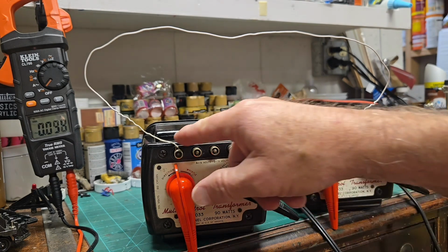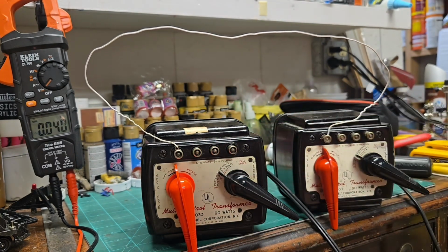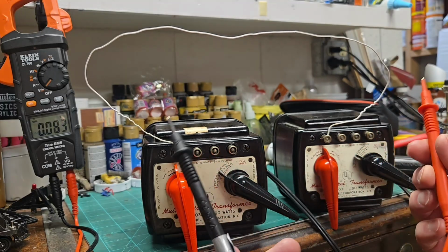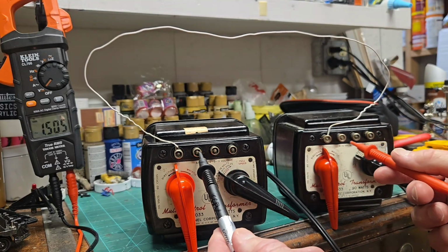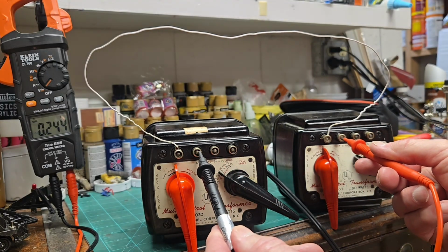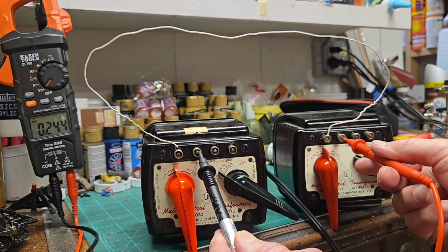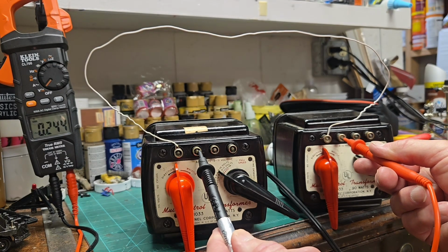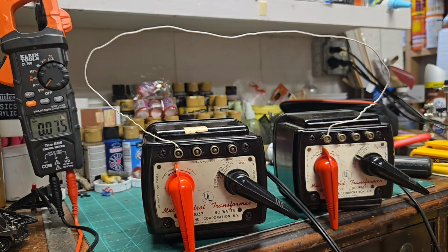It won't matter if it's out of phase, because we'll show you how to change that. Now that I've got U to U, I'm going to check from A to A with my meter. If I go to A and look at the meter, it should be pretty close to 0 - and look at that, it's 0.244. So I'm going to say these transformers are in phase.